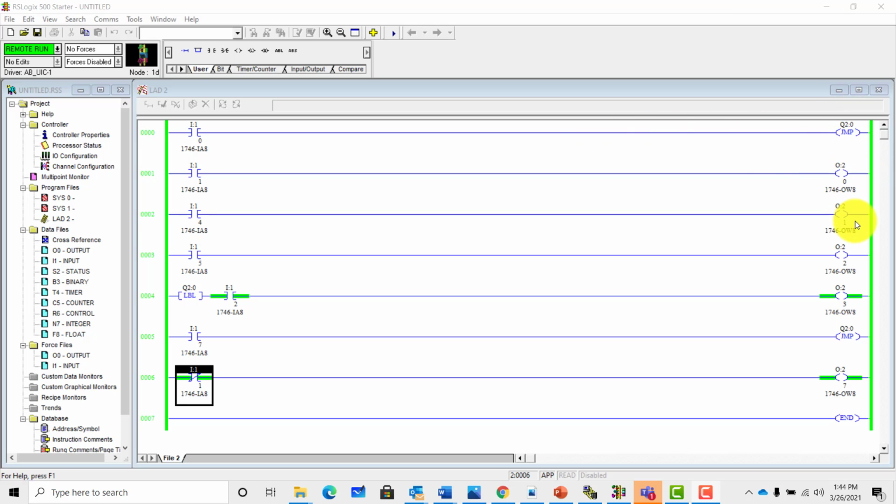But output 2.0 and output 2.1 and output 2.2, all the three outputs within that jump, will not. If you'll look right here, output 2.0, the conditions are true on that rung 001, but we're not changing the output because we are currently in our jump state. But if you look down here, the very same input 1.1 is triggering the output 2.7.